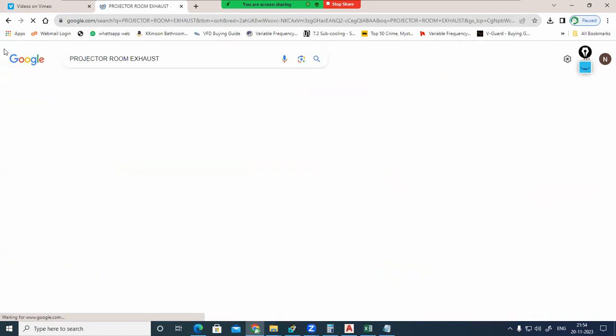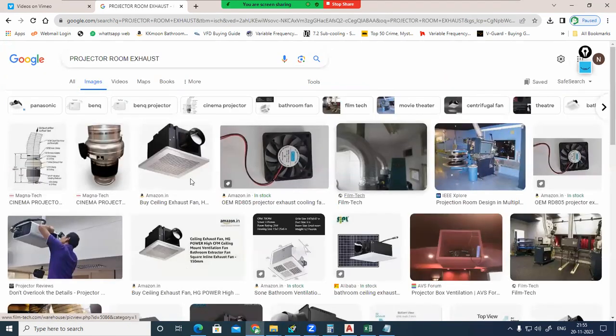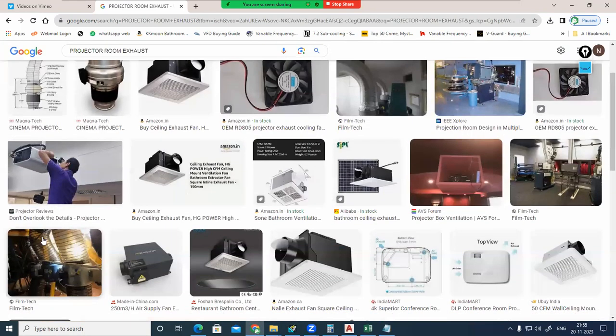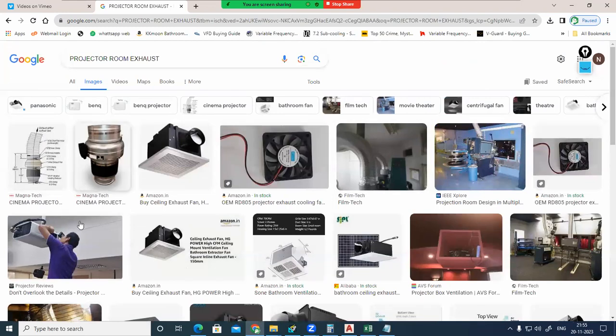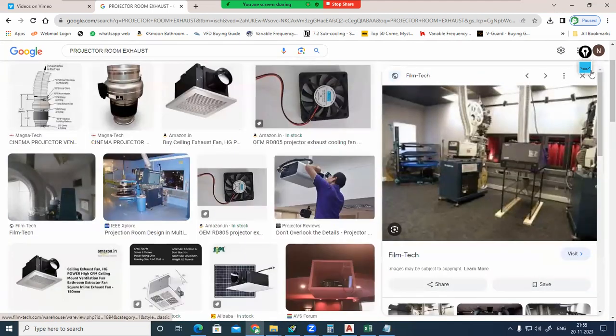Room exhaust will be there in movie theaters. Normally, wall or ceiling hung projectors have an inbuilt exhaust fan, but that fan ejects the heat generated inside the projector to the surroundings, just outside the projector area. So that heat also accumulates within the space, and the AC has to take care of it. But in movie theaters, along with the projector, they will have an exhaust system.